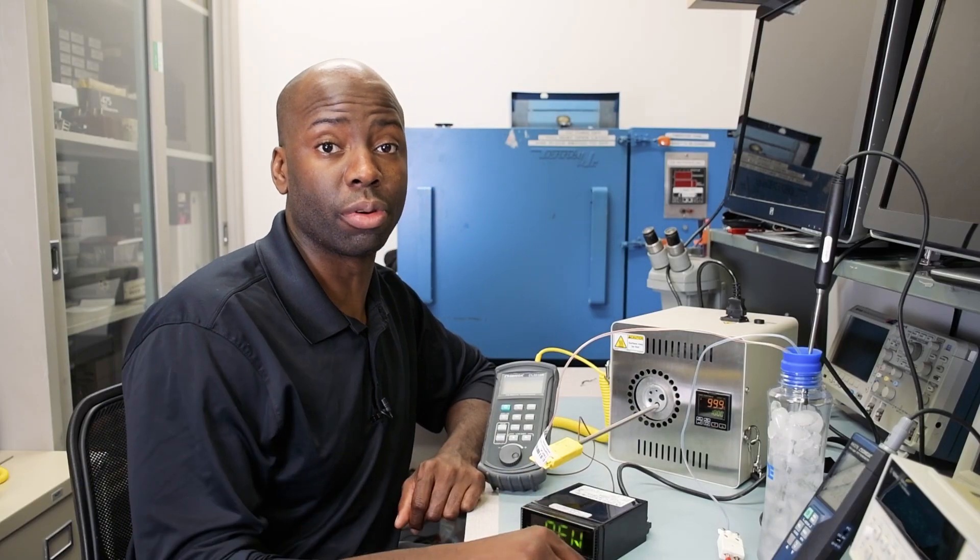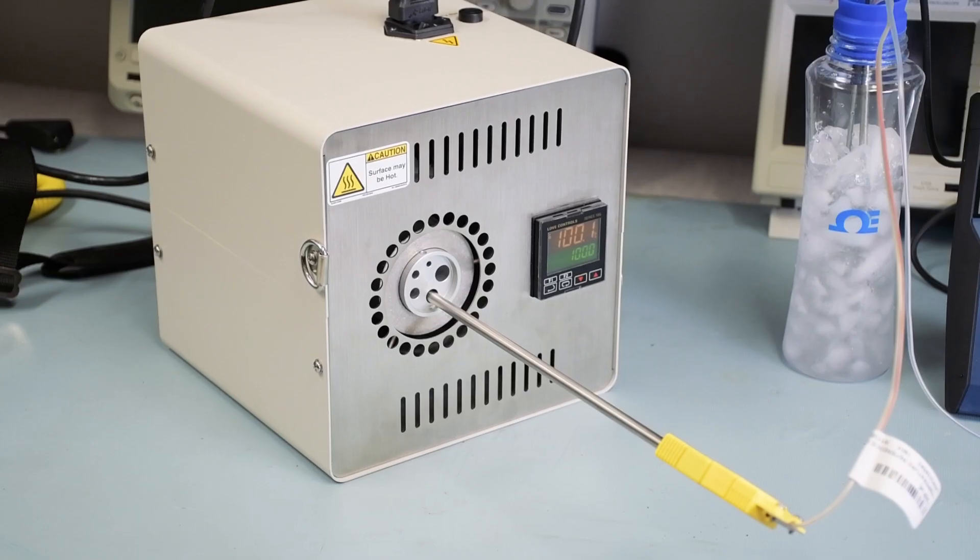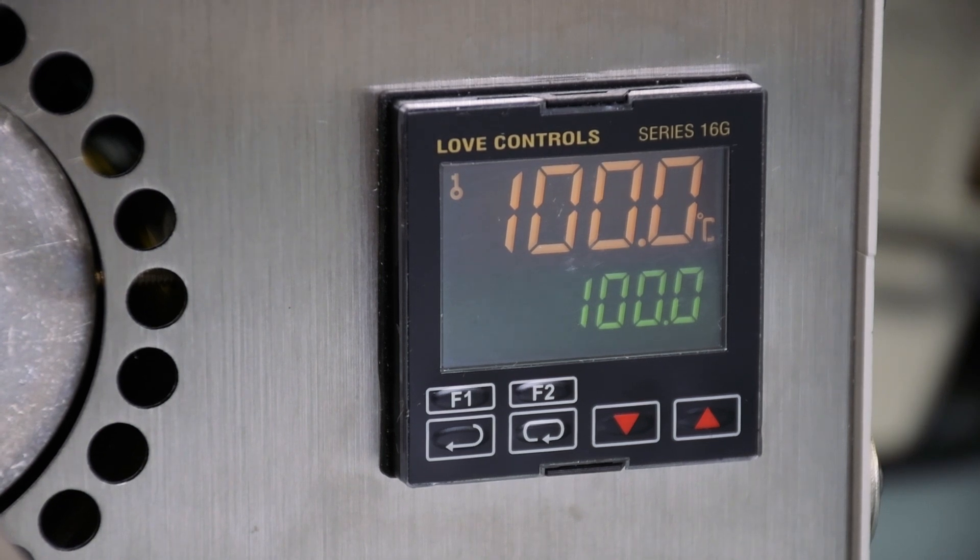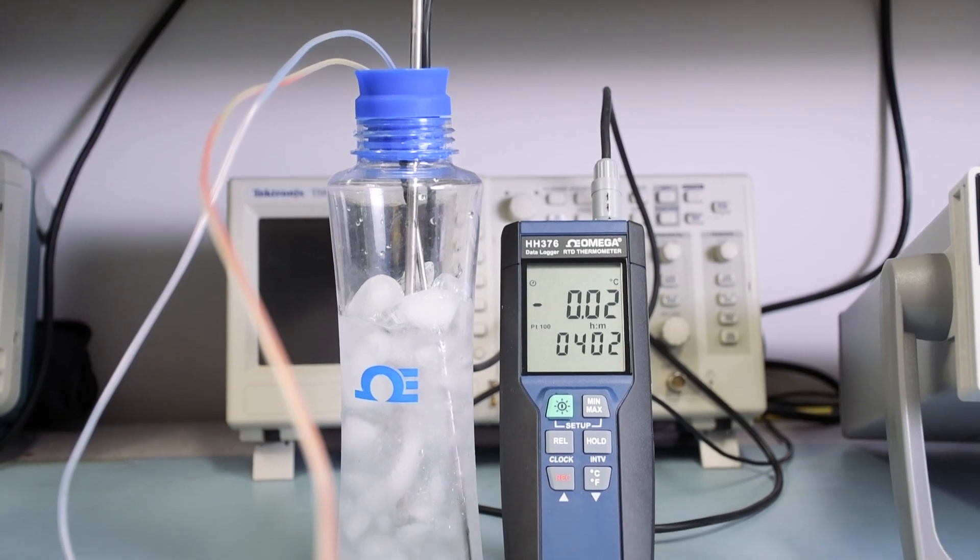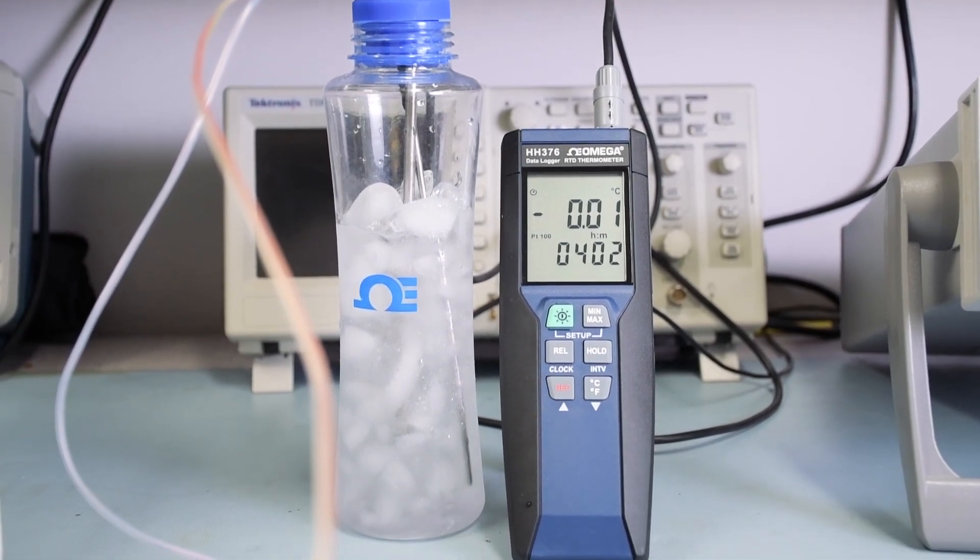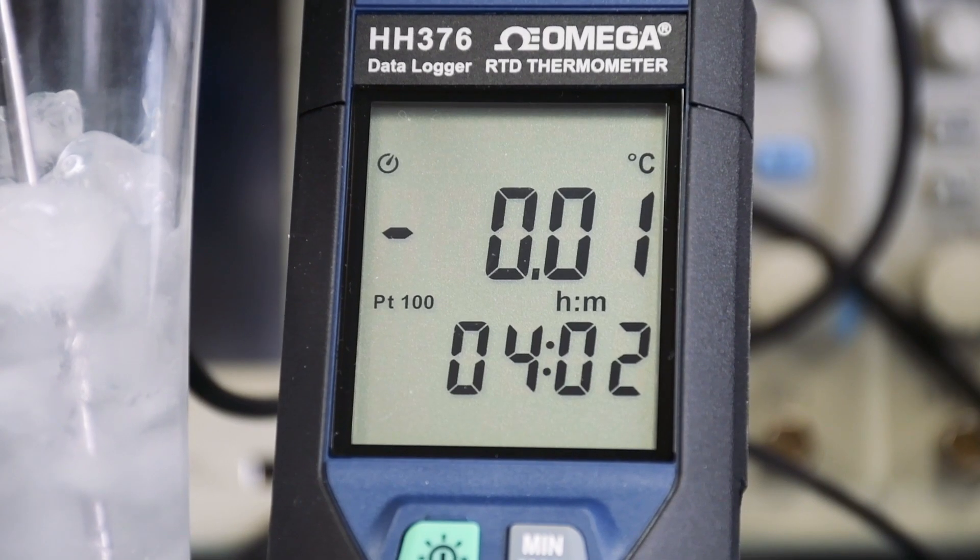So here, we're calibrating a Type-K thermocouple probe. We have it inserted into our dry block, and we have it set for 100 degrees Celsius. We're using this as our reference. We then have the Type-K thermocouple connected to our reference probe that's inserted into an ice bath, maintaining a temperature of 0 degrees Celsius.